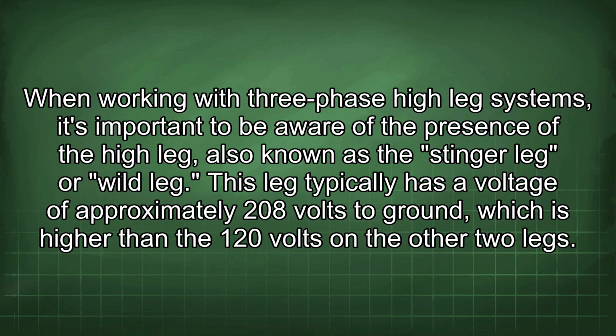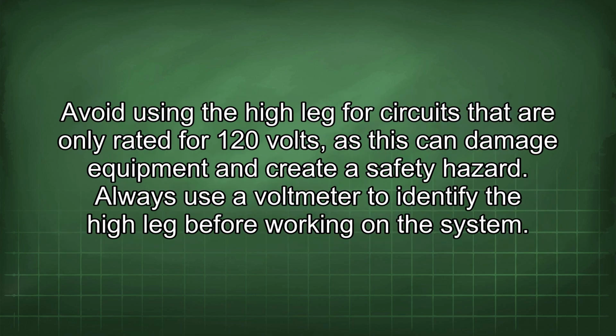When working with three-phase high-leg systems, it's important to be aware of the presence of the high leg, also known as the stinger leg or wild leg. This leg typically has a voltage of approximately 208 volts to ground, which is higher than the 120 volts on the other two legs. Avoid using the high leg for circuits that are only rated for 120 volts, as this can damage equipment and create a safety hazard. Always use a voltmeter to identify the high leg before working on the system.